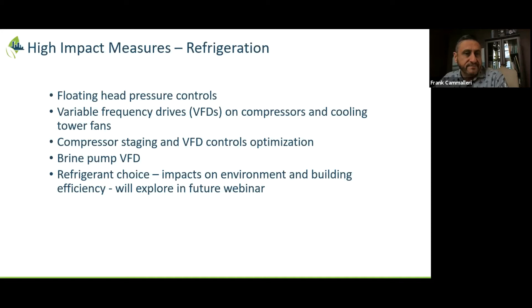If we can go to the next slide. So just a little bit more about the measures we're describing. Floating head pressure, basically, is the concept of varying the head pressure based on the outdoor conditions. Typically, ice rinks will be designed for peak design, based on outside air temperatures that are pretty hot. But in the middle of winter, there's no need to control to that higher head pressure because the temperature outside is a lot colder. So again, varying that, making it a floating head pressure, is really good. We'll be looking at trend logs for how it actually works. One thing to keep in mind is that if there is heat recovery being done within the facility, then this floating head pressure strategy isn't quite as useful and as common, because you need the high pressures to actually get the heat that you need to be used in the facility.